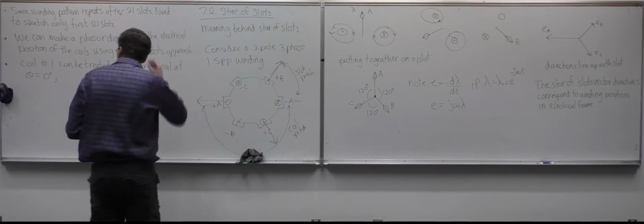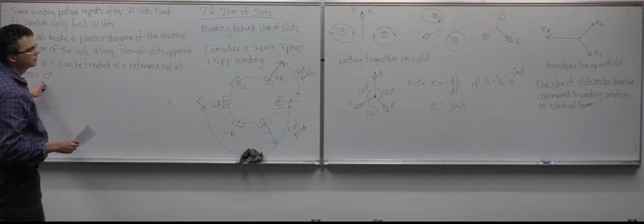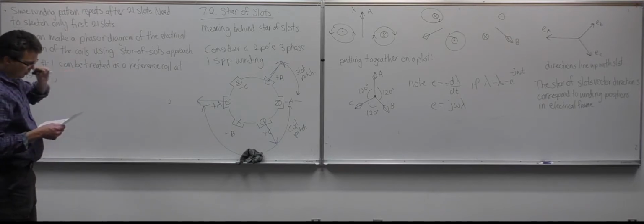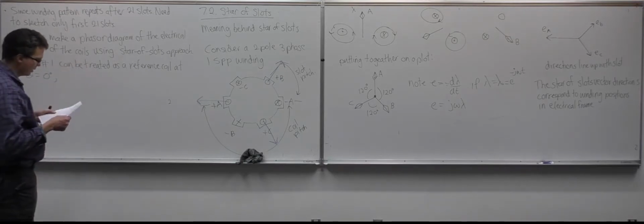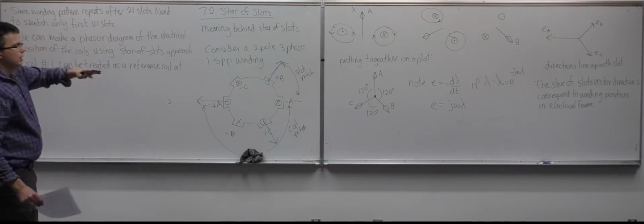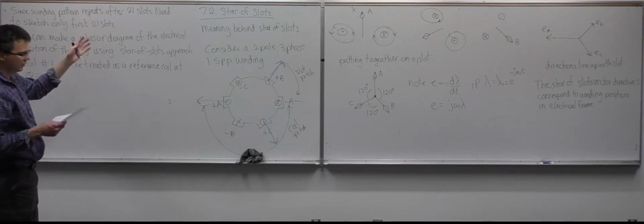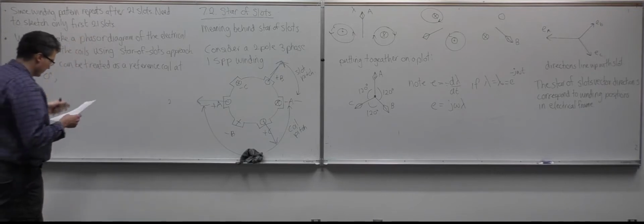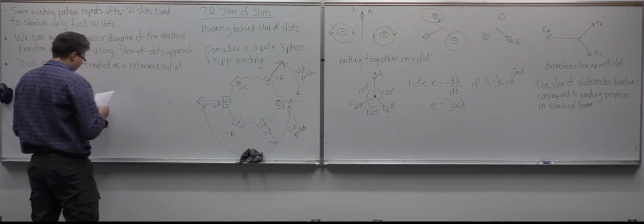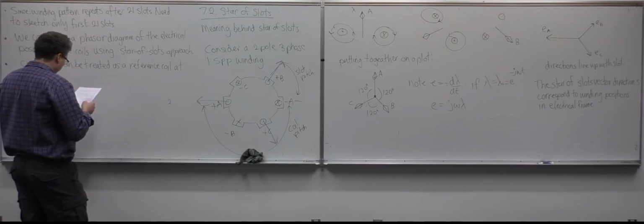So if we choose coil number 1 to be at 0 degrees, that would mean that the next coil going into the next slot would have to be at electrical degrees of 42 and 6/7. The following slot, the third slot, would then be 2 times 42 and 6/7, and so on. I'll show you a drawing of this. But let me just write this.